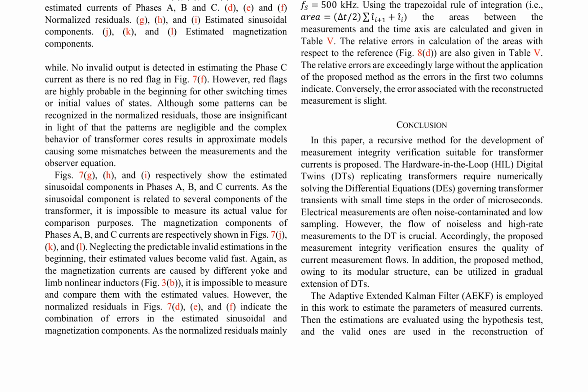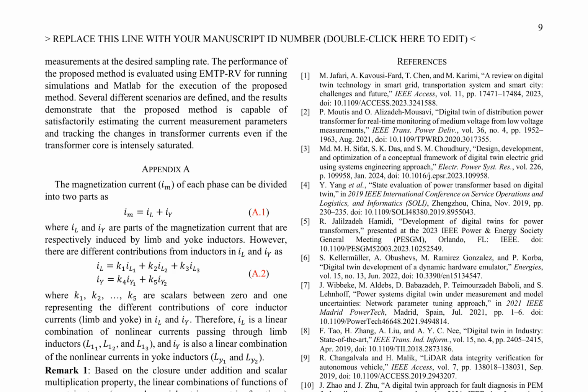The normalized residuals show abrupt changes in currents due to switching, and the estimated sinusoidal and magnetization components are successfully estimated. The overall effect of the proposed method in improving the performance of DTs is demonstrated through a figure showing the measured no-load current of phase A without additive noises, with additive noises, and the reconstructed measurement at a high sampling rate.